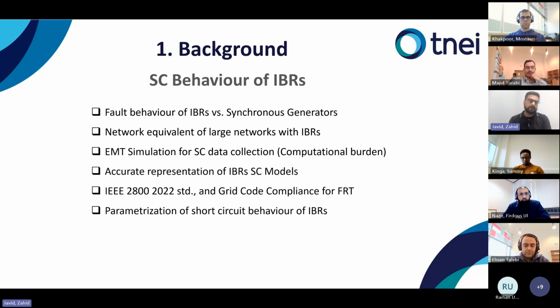And we can parameterize the short circuit behavior, but for that we have to get a large data set using EMT simulation, which is very time consuming. So we developed a short circuit solver that can compute that data set very efficiently in steady state. And then from that data set, we can parameterize the nonlinear behavior of the IBRs during short circuit. We also developed a current limiting strategy to comply with the IEEE 2800-2022 standard, which I will discuss later in detail, and also how to comply with the grid codes when we are developing the FRTs. And at the end, I will discuss how we can parameterize the short circuit behavior of the IBRs.